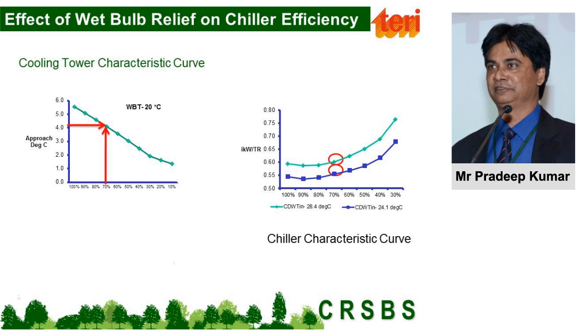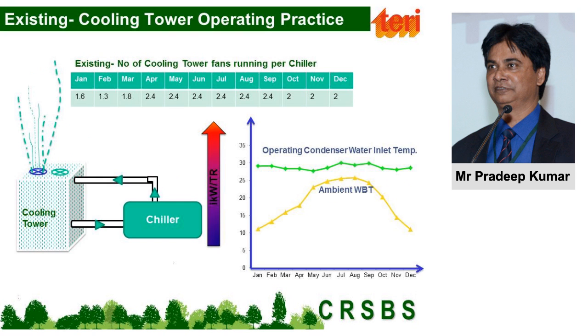We tried to optimize the cooling water temperature or condenser water in temperature. And how it was happening, you know that. We plotted the average temperature. If you take the upper curve, the green one, this is the temperature coming out from the cooling tower, and this is the ambient wet bulb temperature. What we noticed is that, no doubt, from January to May, and again from September to December, the wet bulb was low, but the impact of that was not seen on the water temperature coming out.